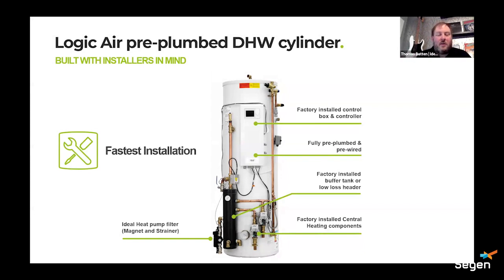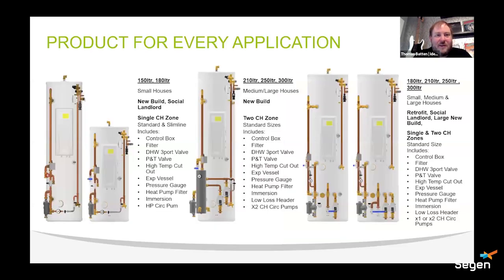So you get a magnetic filter and strainer built onto any of the pre-plumbed cylinders, which negates the need for any other filters or strainers. You can buy a 2-zone with a header, 2-zone with a buffer, single zone with a buffer. There's loads of different options. Anything that's installed on those cylinders is pre-wired for you. So 2-zone pumps on this one, for instance, they're both wired into the control box. I'm getting conscious of time, so I'm going to start trying to skip ahead.